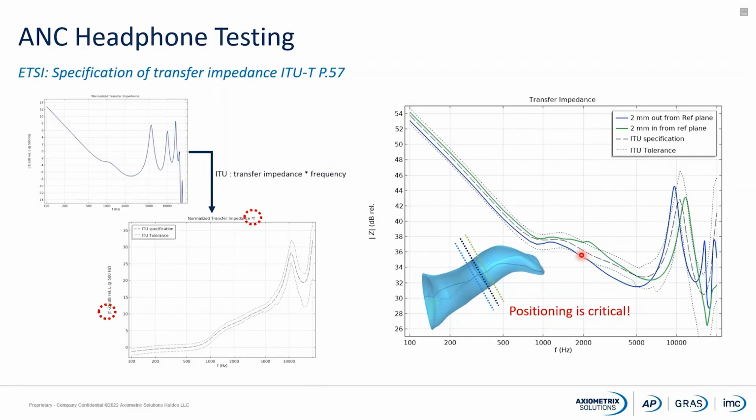So with this, we could say that maybe it's not that important to worry about the particular type of ear that we would like to use if we can't really control the exact position of the device under test inside our artificial ear.